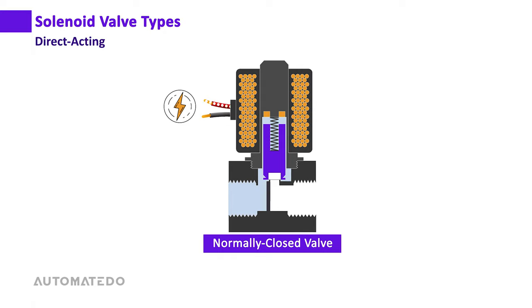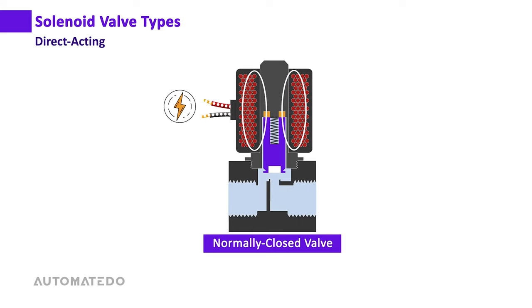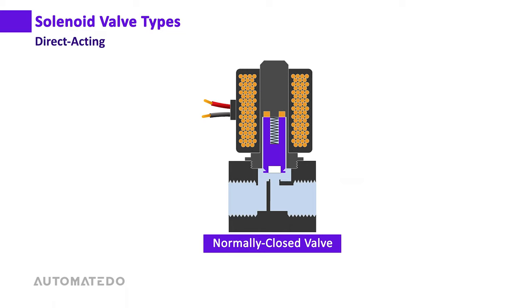When power is applied and current starts flowing through the coil windings, an electromagnetic field builds up. The force of this electromagnetic field causes the plunger to move upwards against the spring, so the orifice opens and allows the media to pass through.